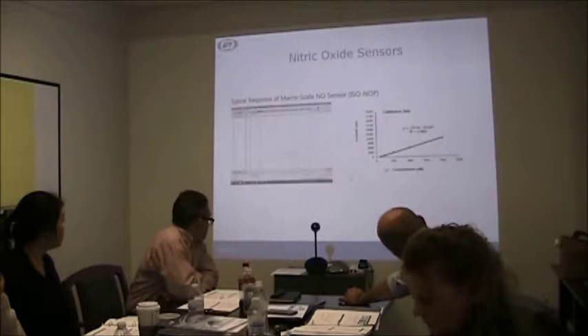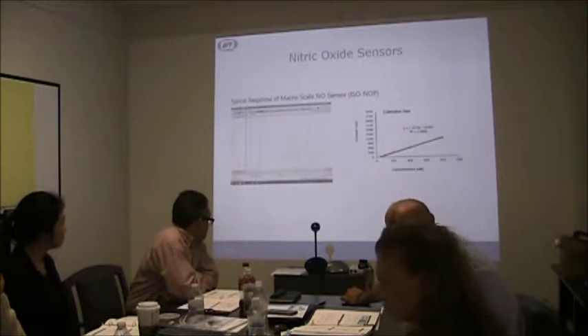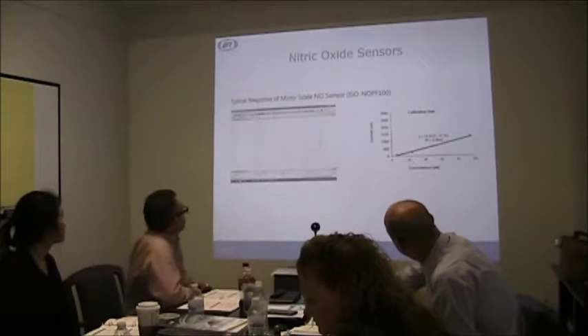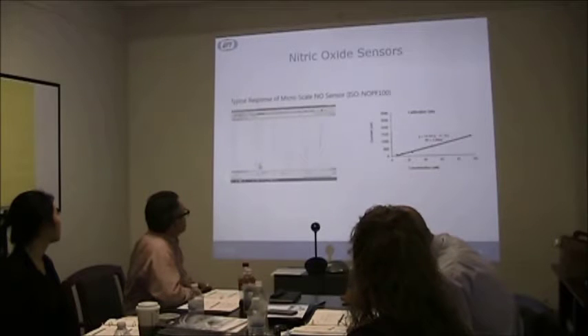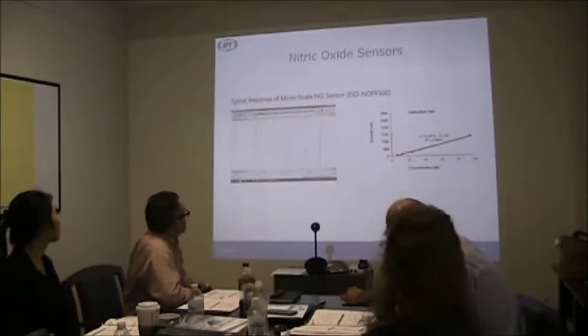We have this plotted as current versus concentration in the nanomolar range. The next slide I will show you is also a nitric oxide sensor. This is our flexible 100 micron nitric oxide sensor. Again, it's a little bit noisier than the previous slide, but the same concept applies: when you have an injection and nitric oxide is being produced, you see this rise in current. Then when it starts to decompose and come down, you double the concentration, and the height of the curve doubles.